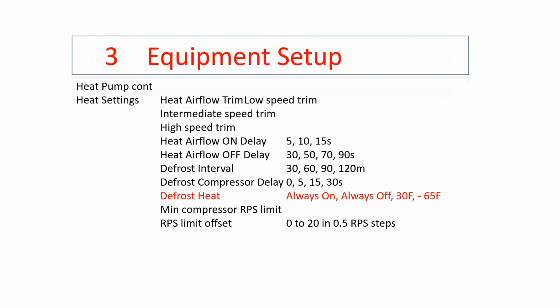Our defrost heat we can set for always on, always off, or we can tell it when to run the defrost heat. Keep in mind, this ships in the off position for efficiency. You want the defrost heat to be able to run to temper the defrost. You'll have to turn that on.